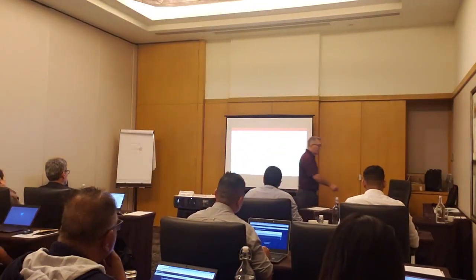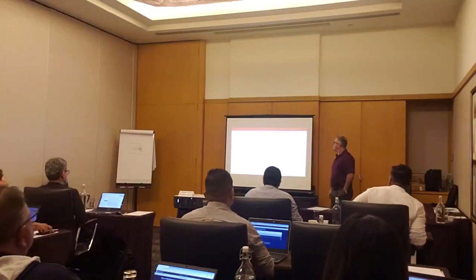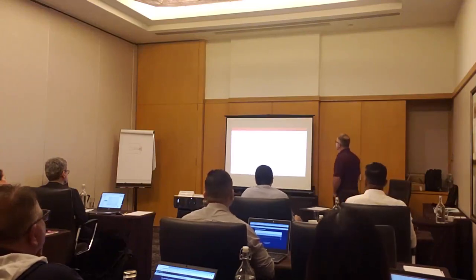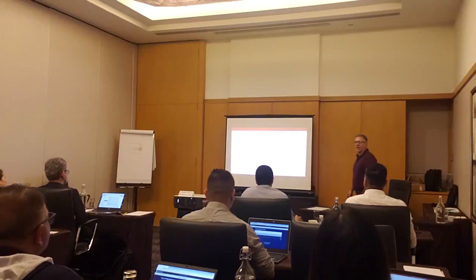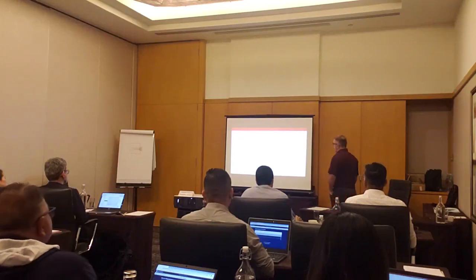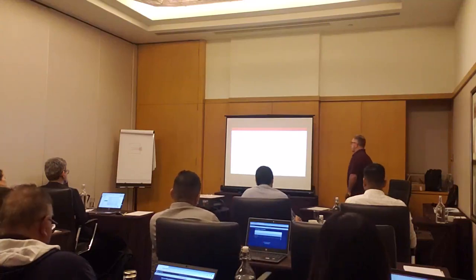So, also had some questions yesterday that I promised to answer this morning. The first one, what's the time required for an electric pump to run during the monthly operational test, according to NFPA 25? In Chapter 8, which goes over fire pumps and the standards for that, the testing is found in Chapter 8, Section 3.2.3. Electric pump shall run a minimum of 10 minutes, and the diesel pump shall run a minimum of 30 minutes. Okay?